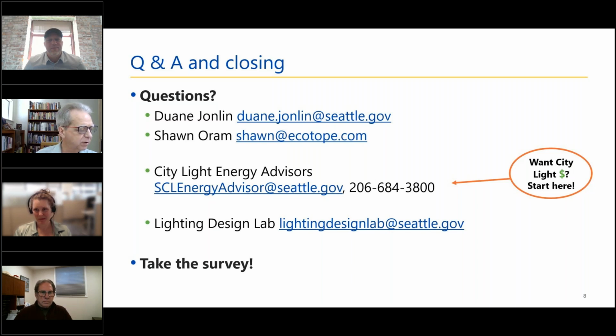Katie, to answer your first question, C404.7.1.2, there's an exception at the bottom of that section that exempts R and I occupancies from that control. Okay, I already deleted the question. I think it was Thomas that asked that. So Thomas, I hope you heard that.